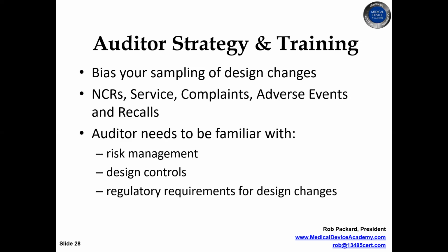Ideally, if you have multiple design team leads, you could have them audit each other's files as well as participate as independent reviewers. But you can't audit your own work. So you might need an outside auditor to come in and audit that if you don't have anybody in the company that isn't working on the project and is qualified as an auditor and knows design. A lot of small companies, that is the case, and we'll do an audit of design controls when we do an independent audit for them.